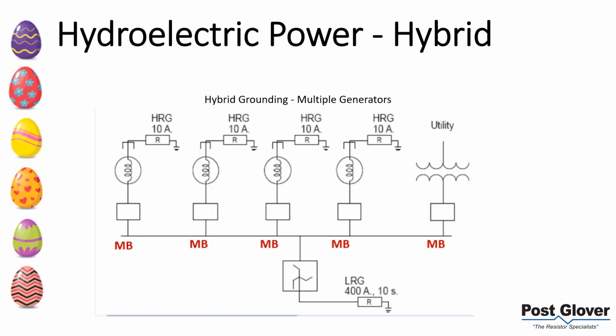To finish the point, this is a common application when you have parallel generators. You have your zigzag transformer, you have your 400 amp 10-second LRG, which hangs off the bus, and then you essentially have an additive ground fault current, 440 amps, for a load side fault. And if you have internal generator faults, you would detect them through the same type of relaying I mentioned. You would open your breaker and wind down separately and safely at 10 amps. So that's the idea. That first graph I showed you, which talked about the extra damage, this would take care of all that. So I just want to bring up those two possibilities.